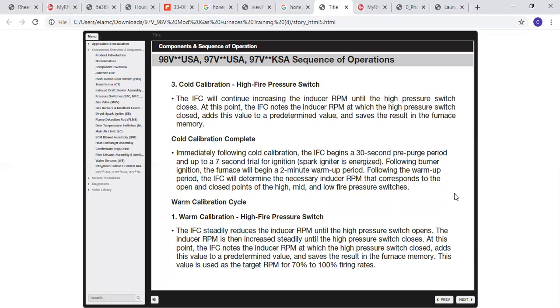Immediately following the cold calibration, the IFC control board begins a 30-second pre-purge period and up to a 7-second trial for ignition. Following burner ignition, the furnace will begin a 2-minute warm-up period. Following the warm-up period, the IFC will determine the necessary RPM that corresponds to the open and close points of the high, the mid, and low pressure switches. During warm calibration, the IFC steadily reduces the RPM until the pressure switch opens. Once it does that, it will note that, add that to the predetermined value, and save that into the memory.